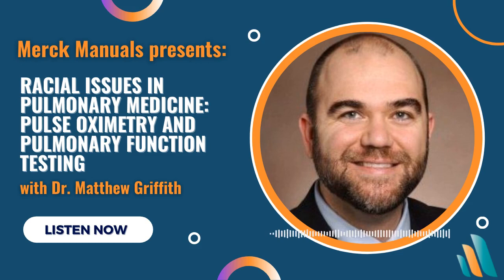So in terms of patients with dark skin tone, there was a pretty good study in 2005 in the Journal of Anesthesiology where Bickler et al. found, using the Fitzpatrick scale of skin tone and exhaled breath mass spectrometry, that commercially available sensors used in the anesthesia field overestimated oxygen saturation in dark-skinned individuals.